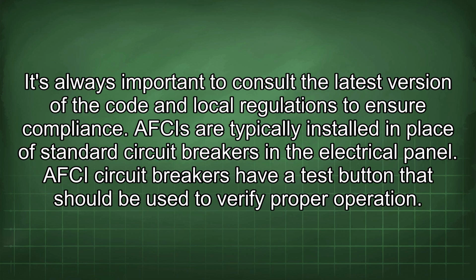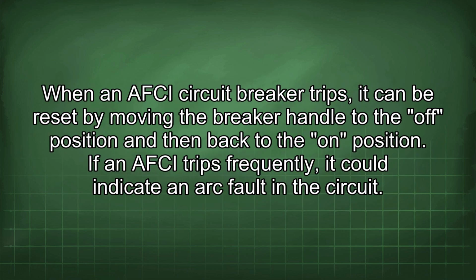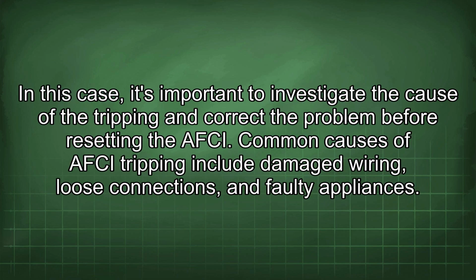AFCIs are typically installed in place of standard circuit breakers in the electrical panel. AFCI circuit breakers have a test button that should be used to verify proper operation. When an AFCI circuit breaker trips, it can be reset by moving the breaker handle to the off position and then back to the on position. If an AFCI trips frequently, it could indicate an arc fault in the circuit. In this case, it's important to investigate the cause of the tripping and correct the problem before resetting the AFCI. Common causes of AFCI tripping include damaged wiring, loose connections, and faulty appliances.